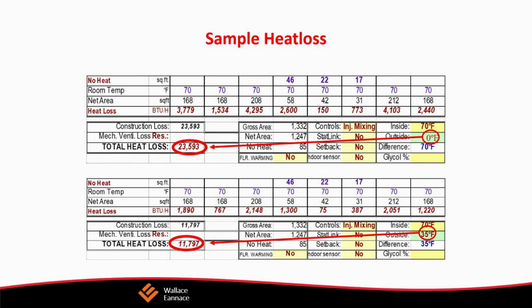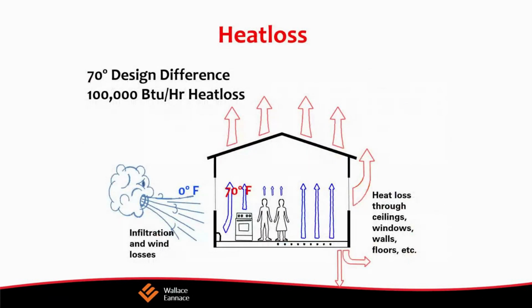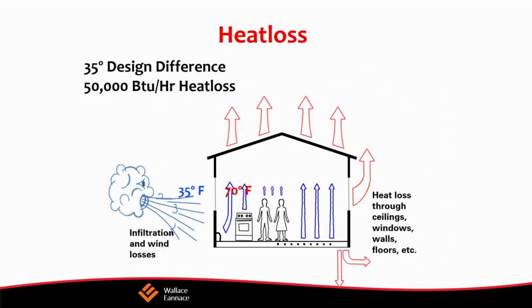Consider what they show. The design conditions almost never occur. A cooling mode is only about 10% of the time. The majority of the time is on a heating mode. So often if we design the system around a cooling system, it's actually backward. Out of 8,000 hours of heating, design conditions occur less than 100 hours. That means 99.9% of the time, the building can be heated with less boiler or less radiation.